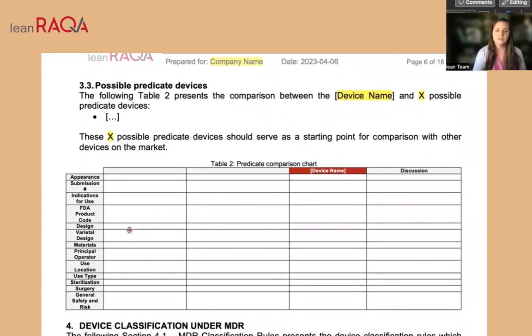If you know that you have a likely 510K requiring device, so a device that requires a submission to FDA that's not a pre-market application, not a PMA, you can start to build that predicate comparison directly in this document. What's really nice about this is you can take this argument directly out of this template and start using it in maybe a pre-submission to the FDA if you need to confirm a predicate strategy or bench test requirements.